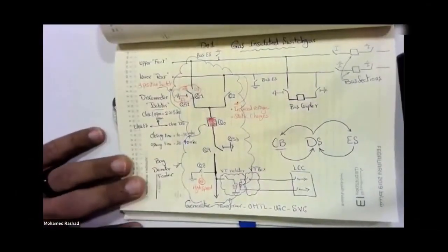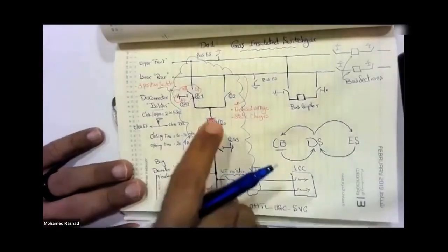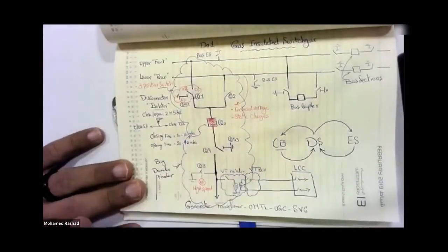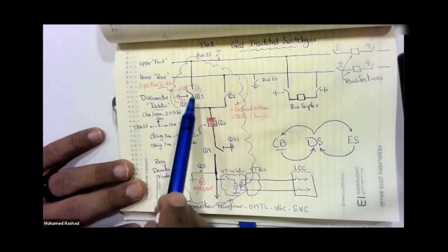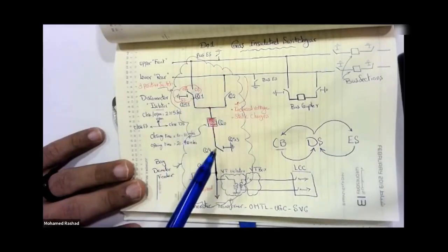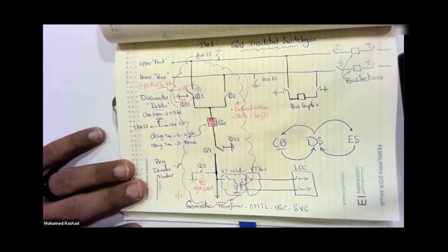Now chill and sneak in here like this. I just told you to close this breaker. I saw the synchronization. Yes, I saw the synchronization. Okay, so what's the other condition? We agreed that you should have Q1 or Q2 closed, and with Q9, it should be closed. Is that good? That's good if you're talking to me about the feeder.